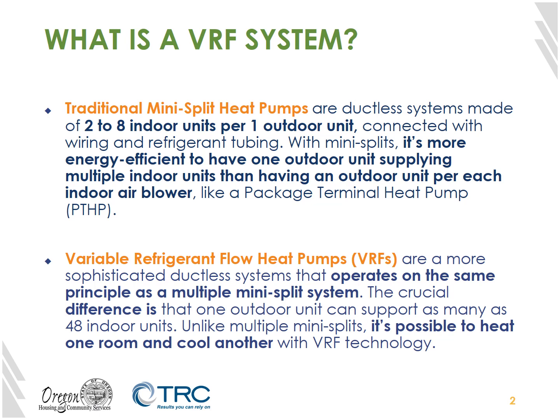They really are designed to be more of a 1-to-1 or 1-to-2 outdoor to indoor unit system. It allows you to work independently in either multifamily or single family scenarios, or even small business, and really control small areas at a time. Whereas the full variable refrigerant flow system operates on the same basic principles as multi-split, but you can actually heat and cool at the same time, which we'll go into in just a minute, in different zones of the building, as well as a single outdoor unit can control up to as many as 48 indoor units. So you can begin to imagine the application of a full VRF system is going to lean more towards multifamily and commercial properties, where the desire is to control large amounts of a building or multiple zones with a single outdoor unit.